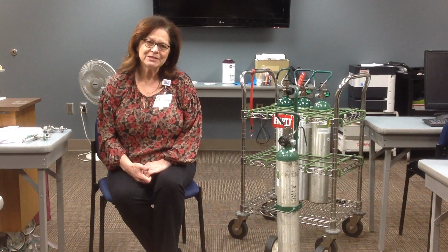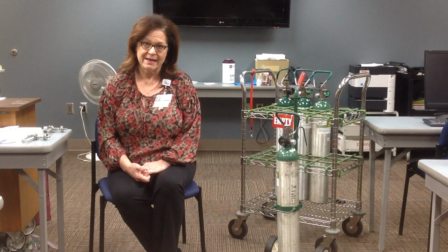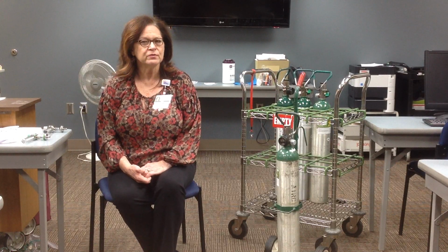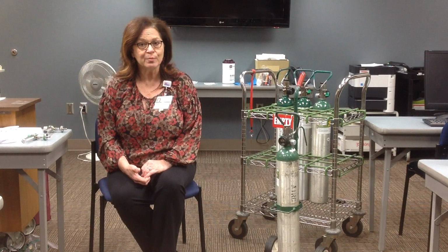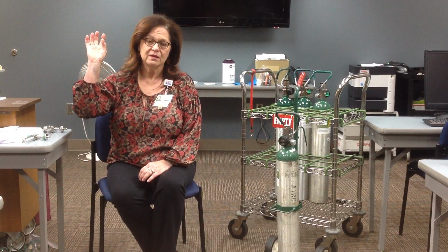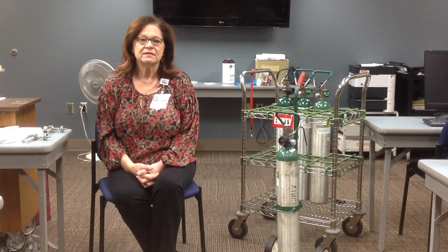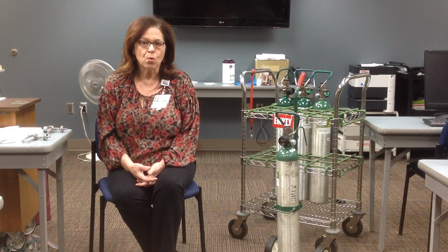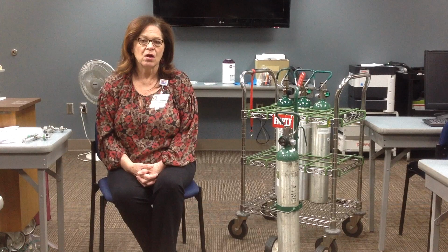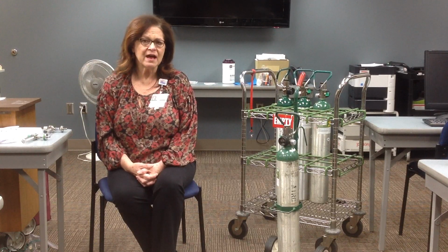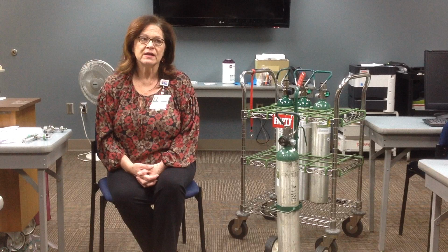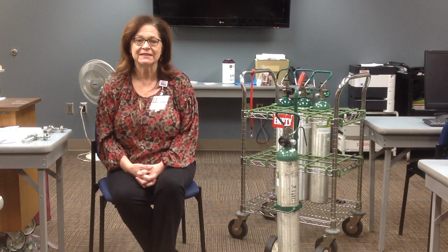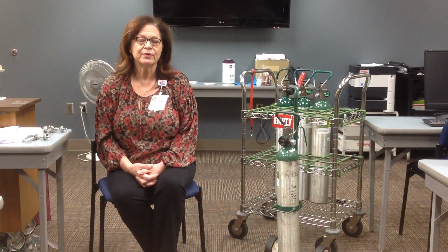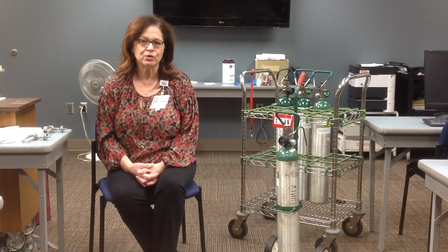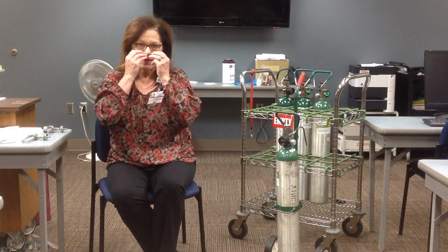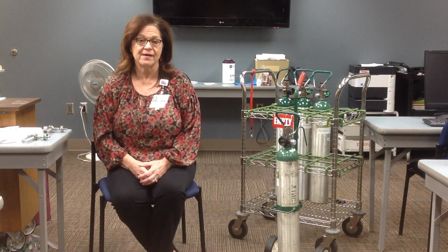We don't use those as much anymore now that we have the Oxy Mask. Before, when we used the non-rebreathers, we would use that high-flow nasal cannula on your patient that kept removing that non-rebreather, and they did well on it, but now we don't use it quite as much. We also have what we call an OptiFlow, which is a high-flow nasal cannula that runs from 10 to 60 liters a minute. It runs through a ventilator heater, so that gas is heated and humidified. Has a very large interface, almost like a nasal CPAP device.